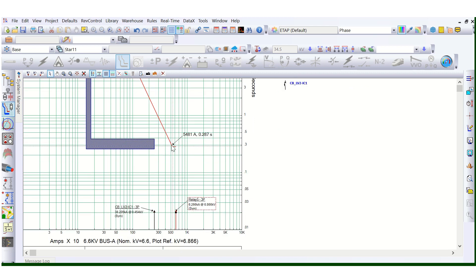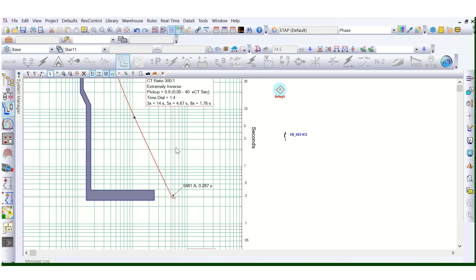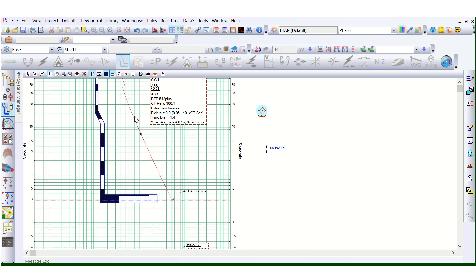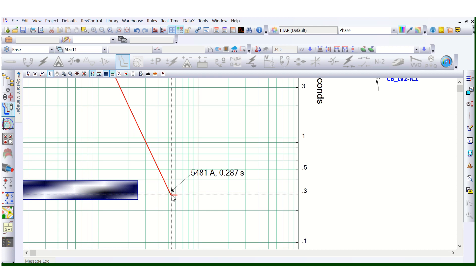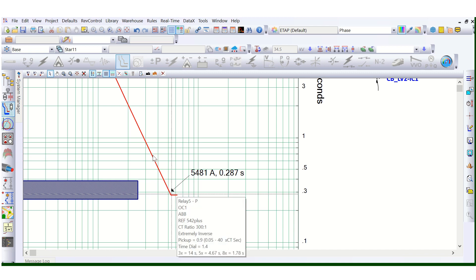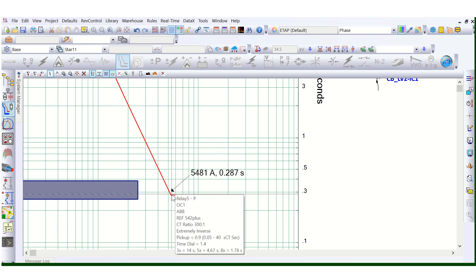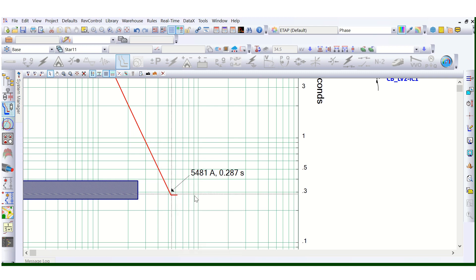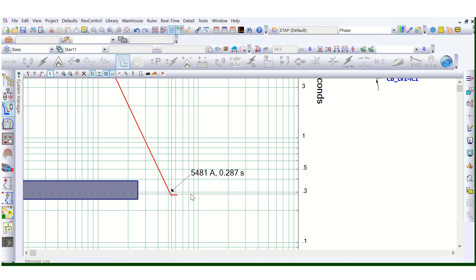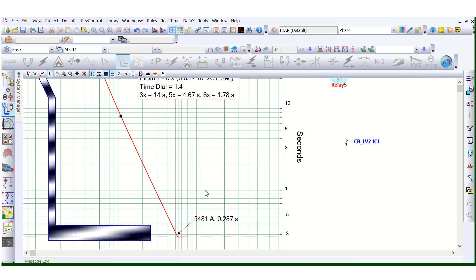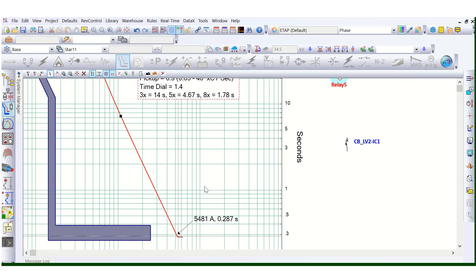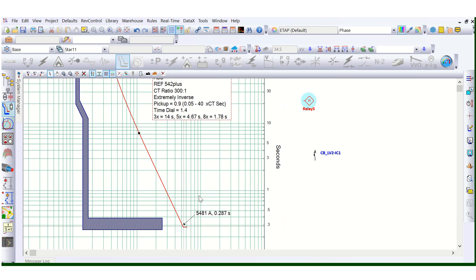The curve is clipped here because my short circuit current is only 6.266 kilo amps. So for IDMT 51 relay, up to a certain point it will maintain its inverse characteristic, and after that it will follow the definite time characteristic. That's why this is called Inverse Definite Minimum Time — IDMT.